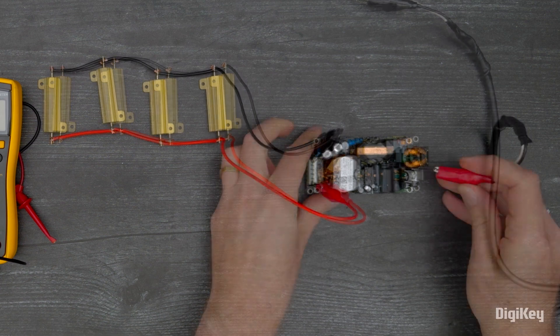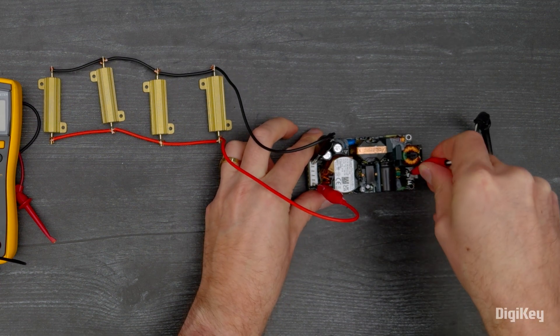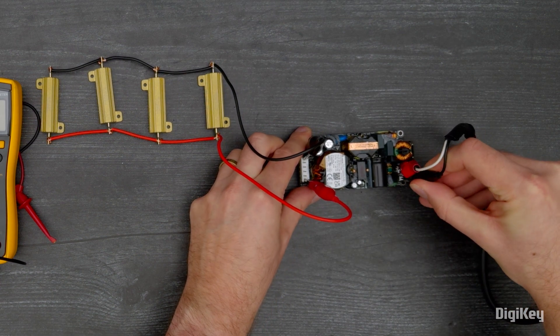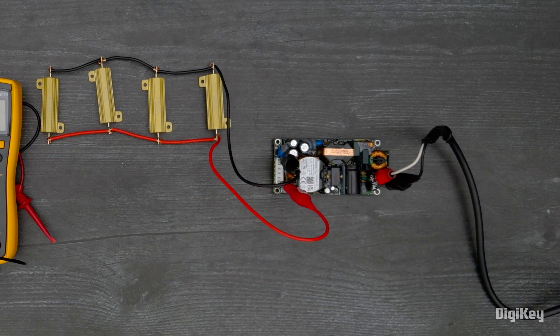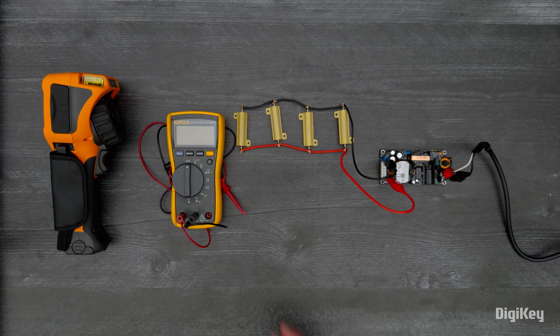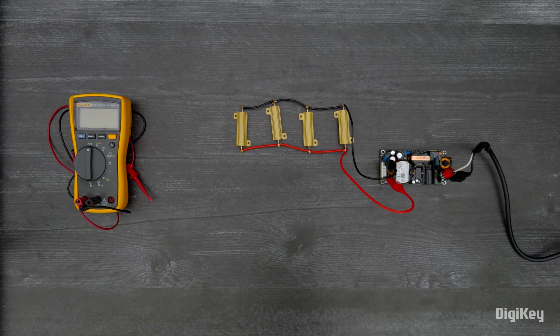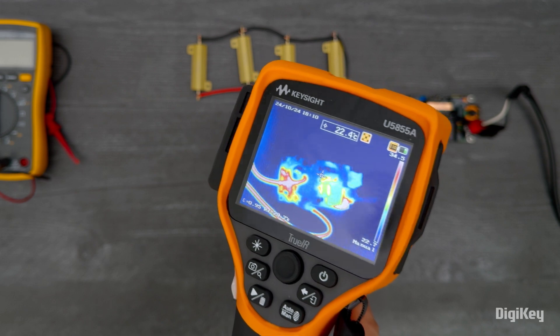Then with power off, connect a 120 volt input to pins one and two on the input connector. Now turn on the input supply and observe the power supply efficiency with thermal imaging.